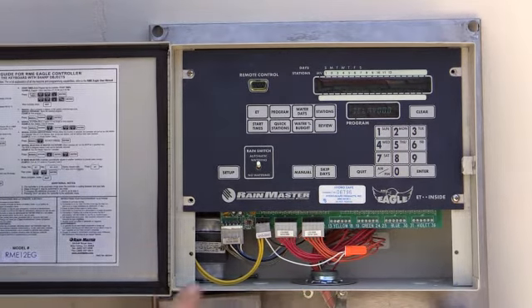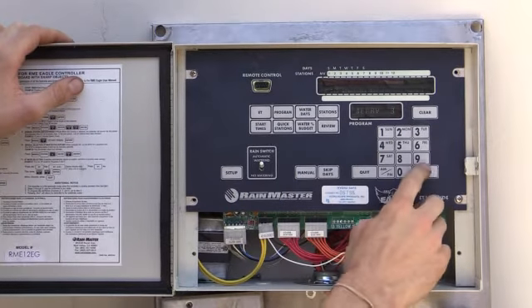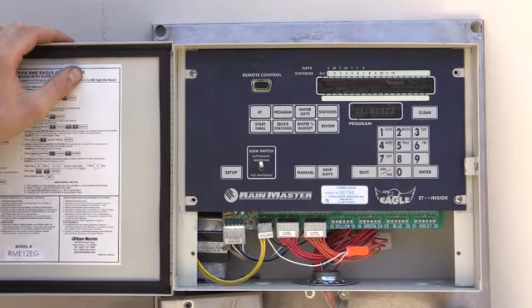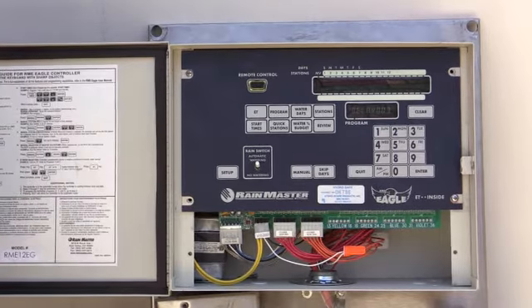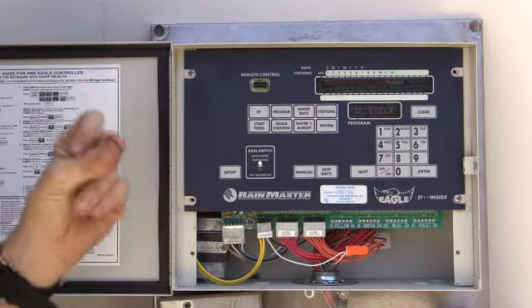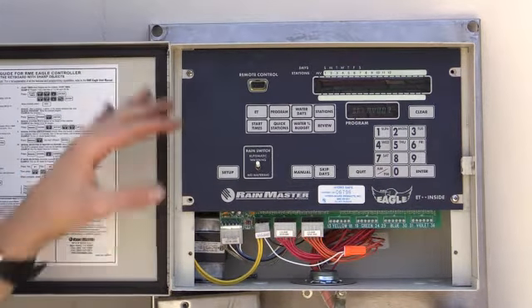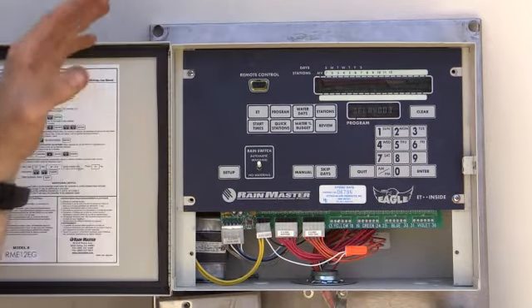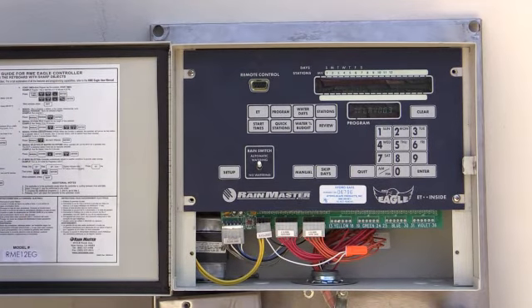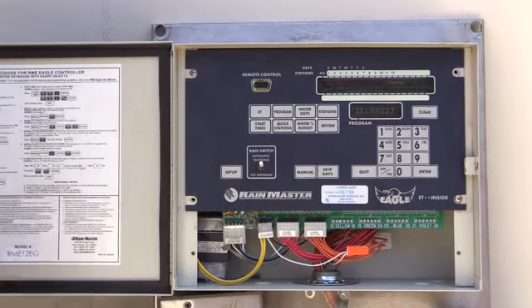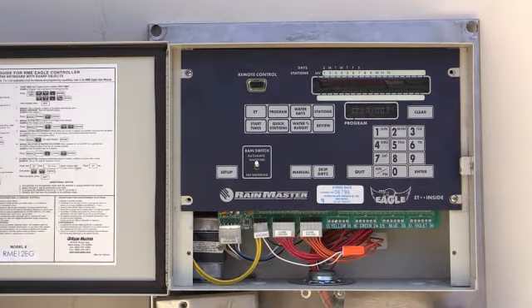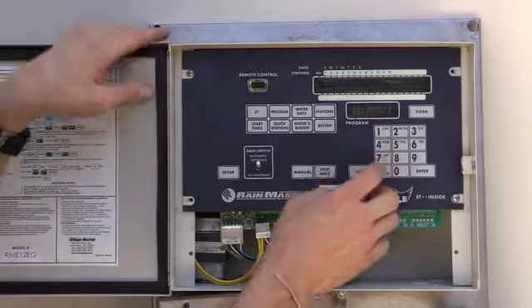So it's a good idea to put this in seconds. I put 3 seconds as my preference. That means when I send power to my valve, when it's time to switch from valve 1 to 2, my controller is going to take a 3-second break. That gives the valve a chance to slow down and close efficiently without the hydraulic demands of turning another valve on.